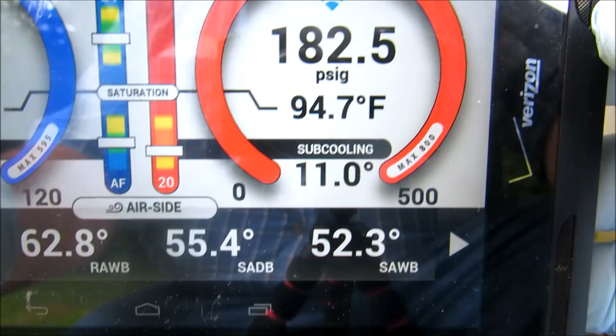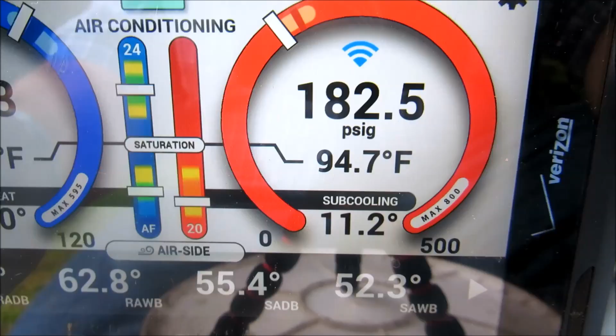Alright guys, you can see I'm pretty close to where I need to be, 11 degrees on the subcool. Superheat, you got to go by subcool.